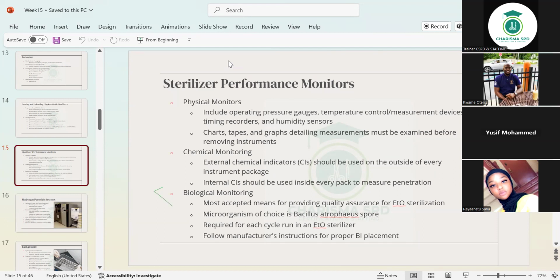So if they take that instrument to the OR and open it, and that indicator was partially cooked or didn't reach the limit as per the IFU, they have to return the instrument. So that's one of the chemical monitoring. External chemical indicators should be used on the outside of every instrument package. So you see that tape that was on it, okay? If they look at it, it could tell them something, good or bad. It has to be used. And then we have the biological indicators.